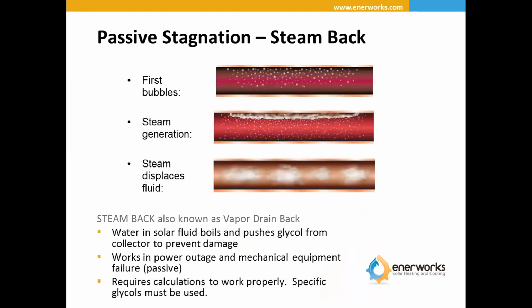How we design for overheat protection: I mentioned the vacuum tube collector that we use is actually made in Germany. I think it might be one of the only ones made outside of China these days. In addition to the temperature limitation built into the collector, you could let it sit all year, overheat every day, and it won't break. But we also designed the system to purge the collector of your solar fluid. So what happens is the water and glycol solution, we pressurize the system so that it'll boil at about 230 degrees. The water boils just before the glycol, and it creates a small amount of steam, which pushes the fluid out of the collector.